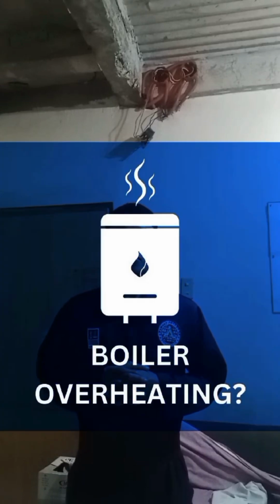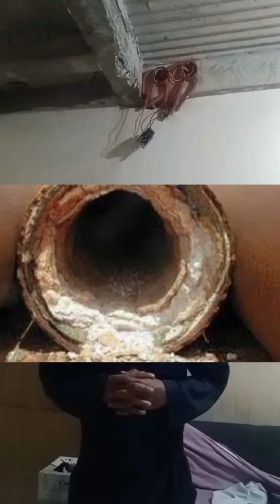Boiler overheating. Overheating is always caused by the presence of some insulating medium between the furnace and water chamber. Causes: Number 1, high degree formation of scale, sludge, mud, and oil. Number 2, poor water circulation. Number 3, feed water shortage. Number 4, local overheating. Number 5, faulty combustion. Number 6, incorrect raising of steam. Number 7, direct flame impingement resulting from this formation and local bulging.